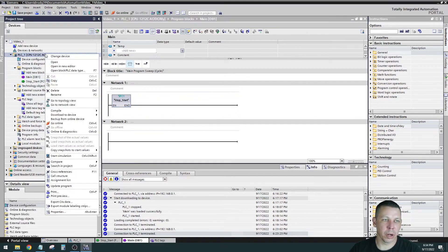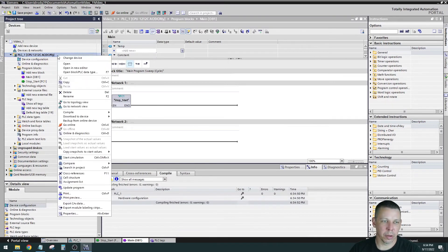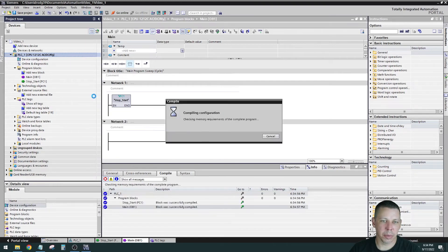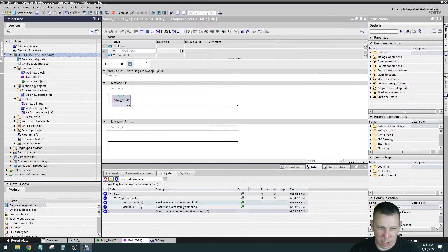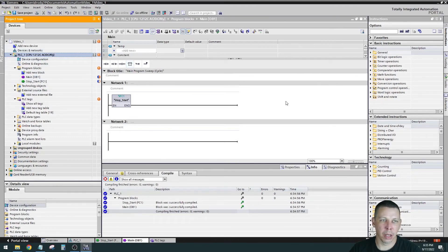Now go to PLC1, right-click, and go to Compile. It gives options for hardware and software. I'll do Hardware Rebuild All and Software Rebuild All to make sure it gets everything. Down here it says the Stop Start Function 1 block was successfully compiled, then OB1 was successfully compiled — it has to compile now because it calls that function. It says 'Finish compiling: errors 0, warnings 0.' That's what we want. Now go online — it went online immediately without searching for the processor.